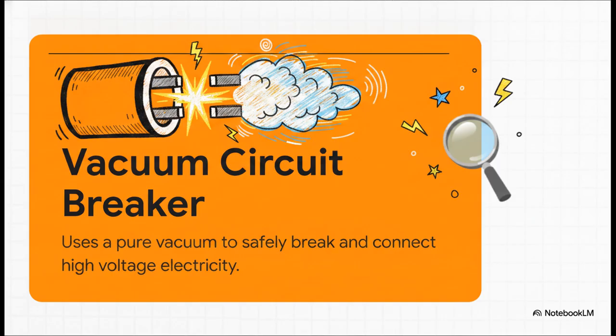So what exactly is a vacuum circuit breaker, or VCB for short? At its core, it's a heavy-duty switching device. But unlike that simple light switch in your kitchen, a VCB uses a pure vacuum as its arc-quenching medium to safely break and connect high-voltage electricity. Since a vacuum is completely empty, it provides exceptionally high insulation. When a highly energized connection is broken inside that vacuum, the resulting electrical arc is extinguished almost instantly. This makes the VCB perfect for critical systems that demand high reliability and low maintenance.